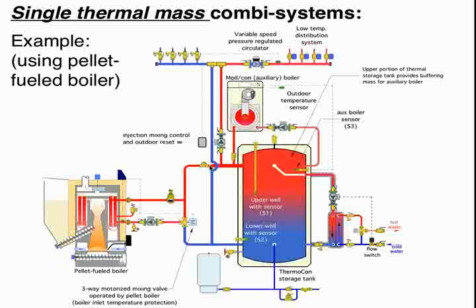Great. While we're on the tank, the glass-lined tanks, how would you compare them relative to a long-term perspective in light of water chemistry versus, say, perhaps a stainless steel tank or even an unpressurized plastic tank? Wow. That's going to be tough. I would think that the glass lining certainly doesn't work against you from the standpoint of applying it in a hydronic system. But if it is a true closed-loop hydronic system, theoretically, you don't need the glass lining. Just a carbon steel tank should work.